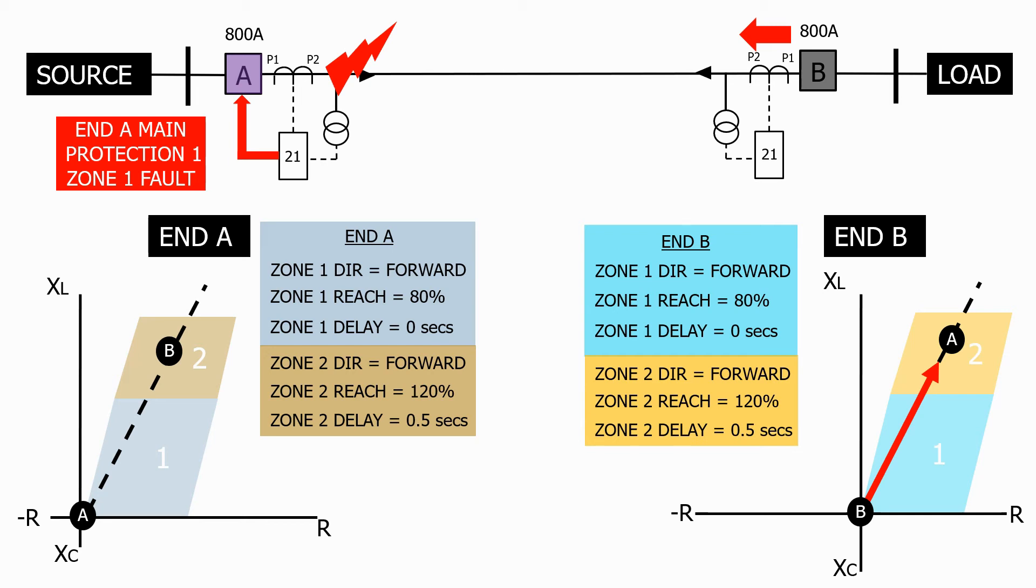The end B impedance relay is still seeing the fault, as fault current is flowing in from end B. It then trips after a 0.5 second time delay, clearing the fault from the system.